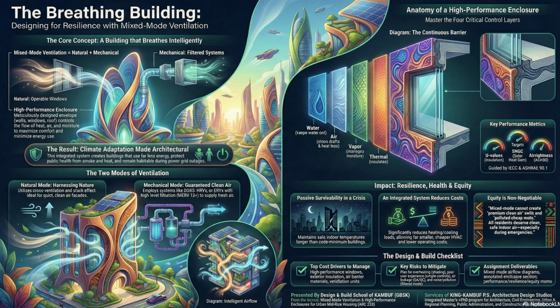Okay, so we know what the climate is going to throw at the building. Now we have to actually build the machine itself, the high-performance enclosure. This is that first line of defense, right? It locks in performance passively before you even turn anything on. That is the critical mindset. If your enclosure is leaky, if it's porous or poorly insulated, you're just signing up for oversized, expensive mechanical equipment that will never, ever achieve real comfort or efficiency. The passive parts have to do the heavy lifting.